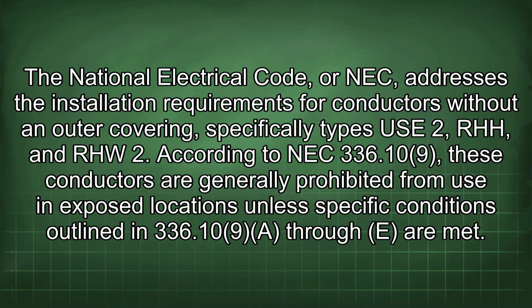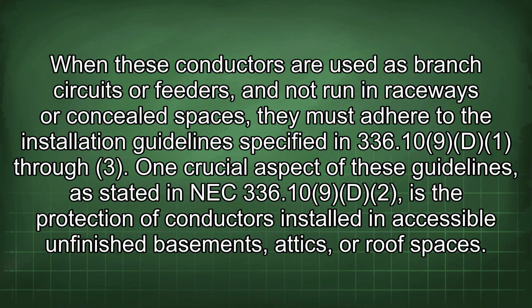The National Electrical Code, or NEC, addresses the installation requirements for conductors without an outer covering, specifically types USE-2, RHH and RHW-2. According to NEC 336.10(9), these conductors are generally prohibited from use in exposed locations unless specific conditions outlined in 336.10(9)(A) through (E) are met. When these conductors are used as branch circuits or feeders and not run in raceways or concealed spaces, they must adhere to the installation guidelines specified in 336.10(9)(D)(1) through (3).